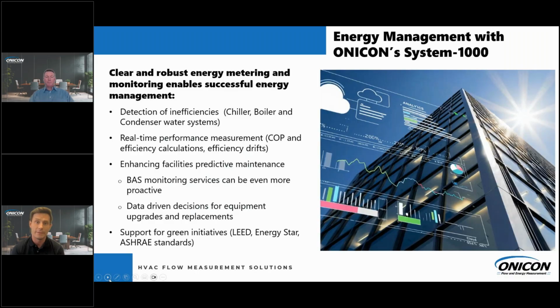If it drops in efficiency points, you can go out there and service that equipment immediately rather than waiting for the next schedule for it to occur. And you can show the value of that. If it were 3 months out, you can show, hey, we boosted this up by 3 percentage points, and you can quantify that to dollars. And let's say it's the flip side. Let's say it's an older boiler and you've been servicing it, but it's dropping in efficiency. Now you can show the reasons and the data-driven decision to replace that boiler because it's dropping in efficiency. You can do a cost analysis to show why it's worth that investment. So by installing it, you can be proactive with your maintenance and provide data-driven decisions for system upgrades and system replacements. Additionally, it supports green initiatives.